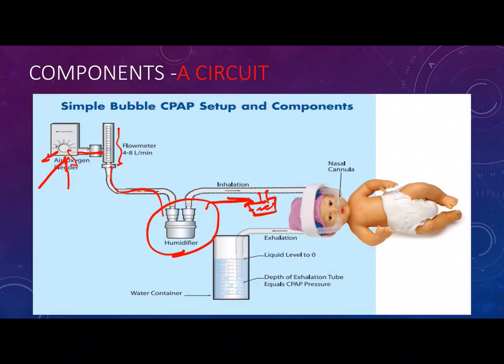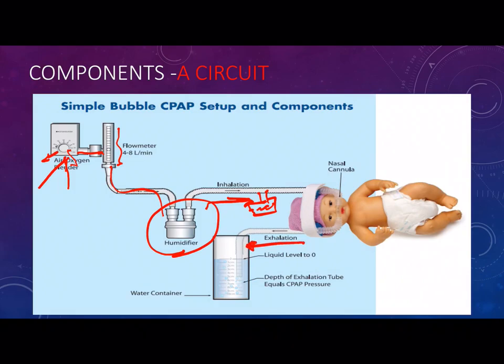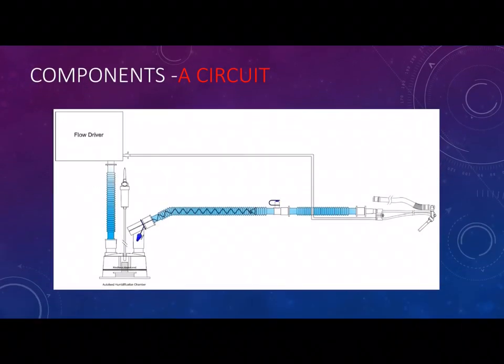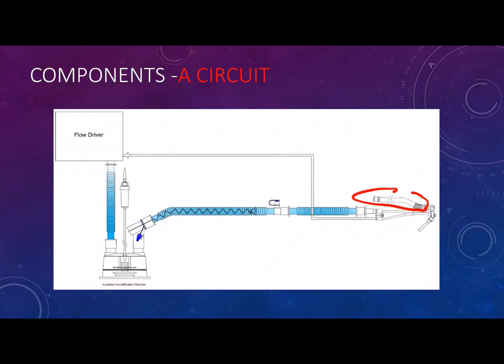After reaching the baby, there is an expiratory limb. In the continuous flow type, the expiratory limb is usually long and ends by submersion under the water seal or is connected to the ventilator. In the variable flow type, the expiratory limb is either very small or even absent in some subtypes.